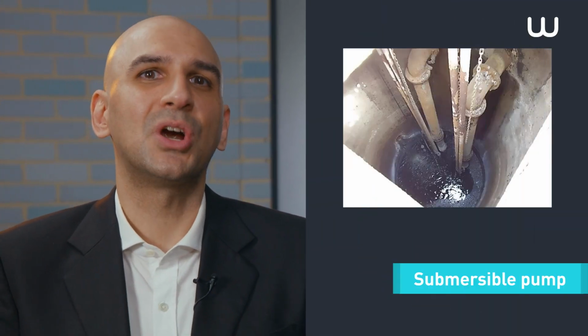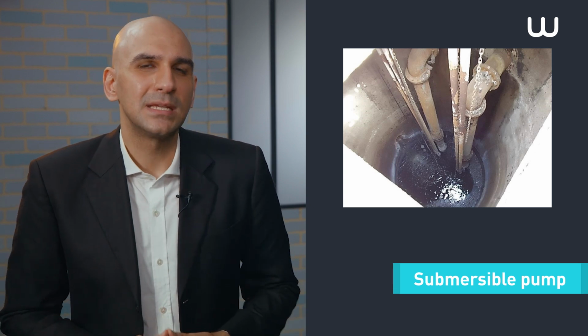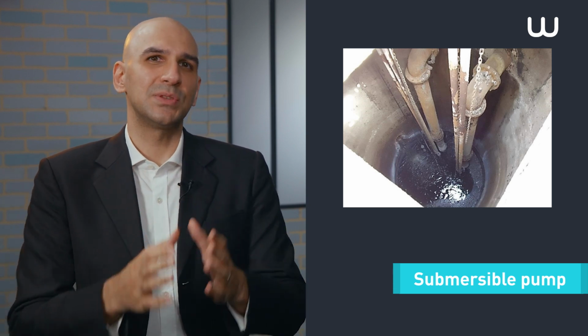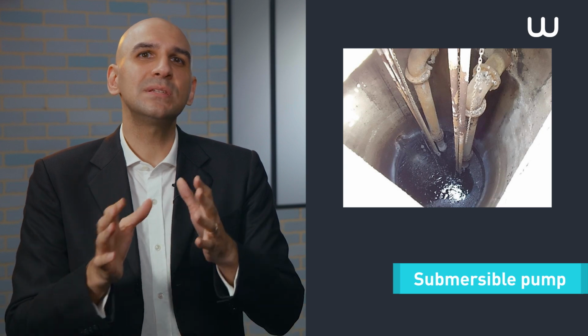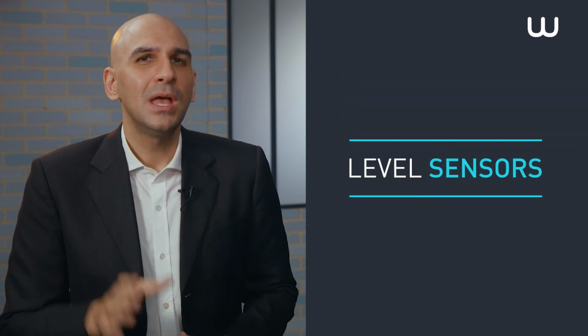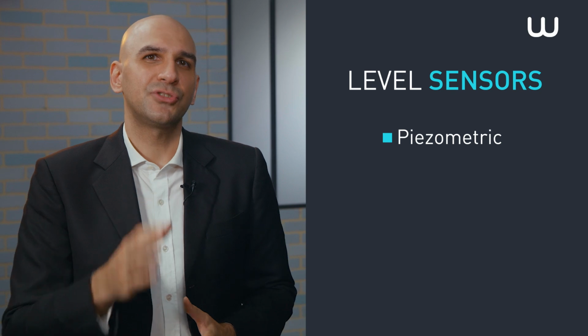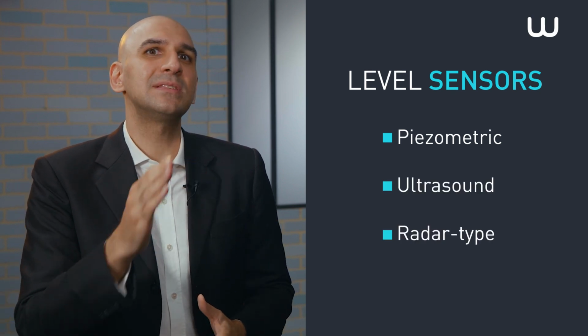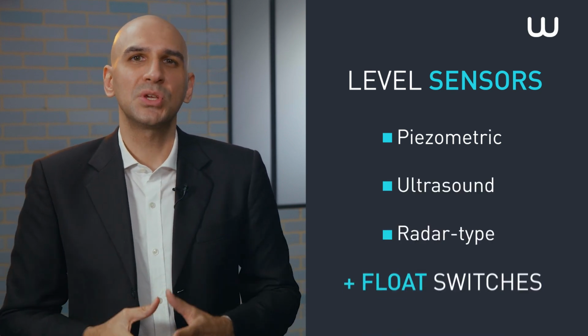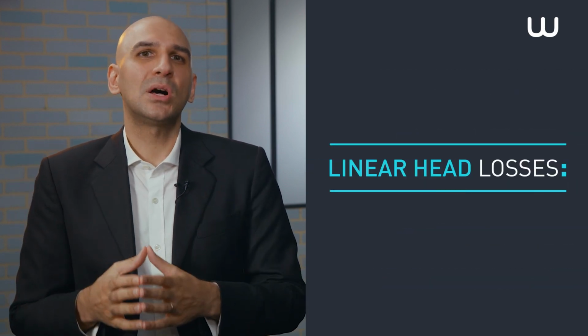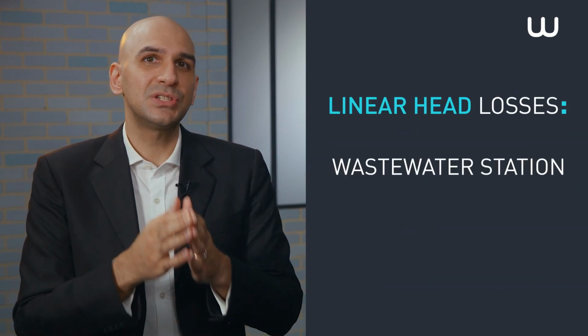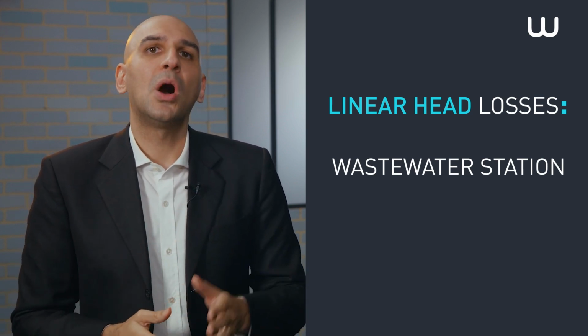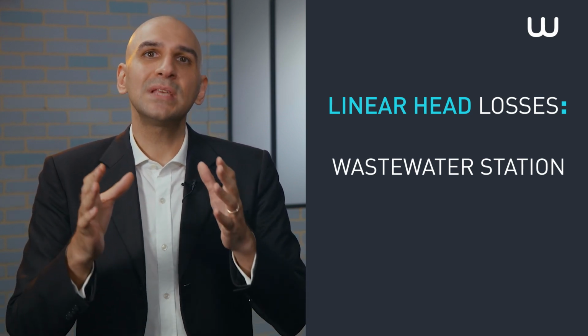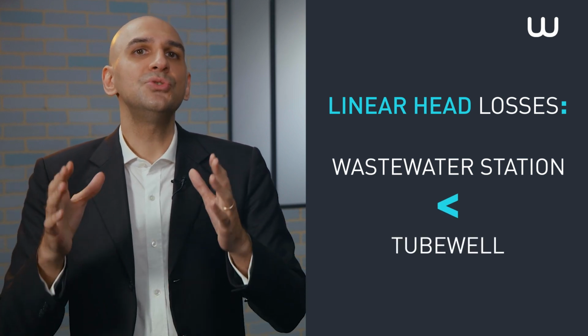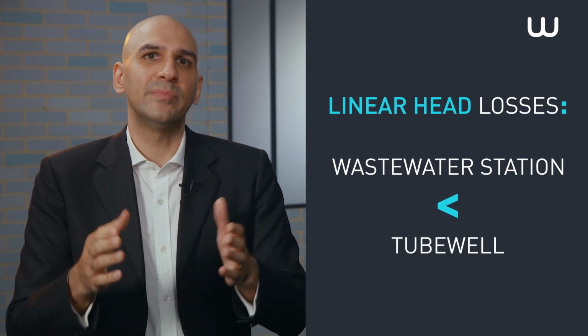Lastly, let us look at a submersible pump in a pumping and discharge station. At this type of site, the pump's startup and shutdown sequences are indexed to the effluent suction tank's level change. Very often, piezometric, ultrasound, or radar type level sensors are found in addition to float switches. The linear head losses to be calculated in a wastewater station during an energy audit are significantly lower than those identified in a tube well due to the difference in the depth at which pumps have been installed.